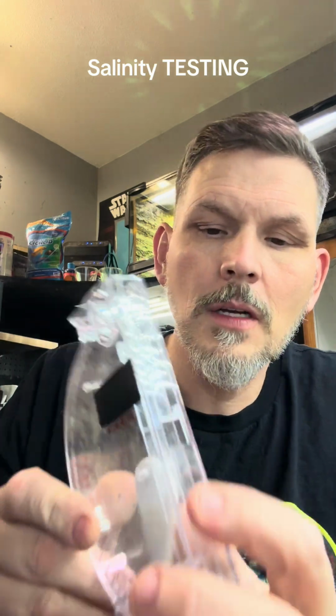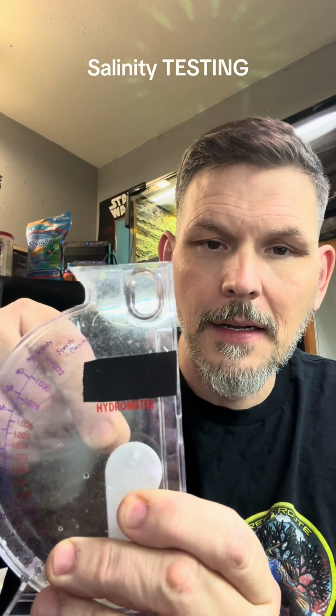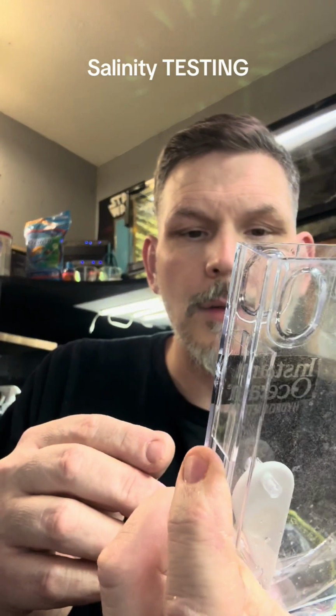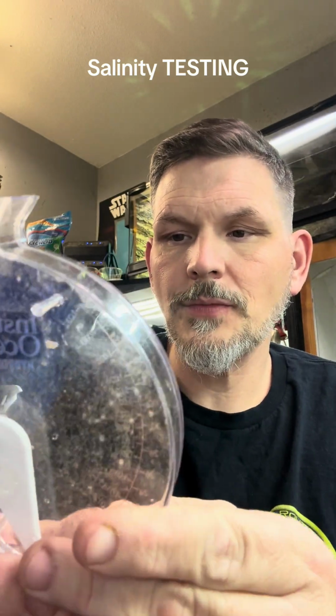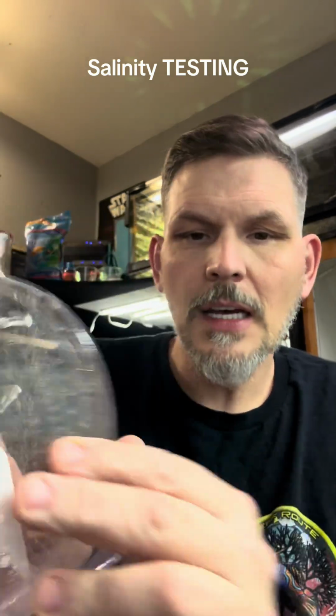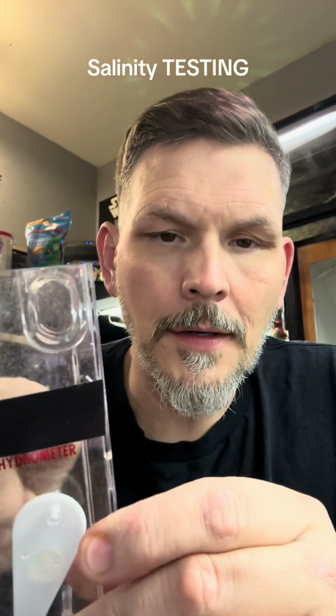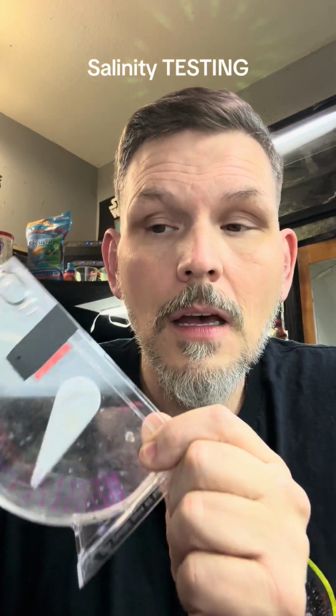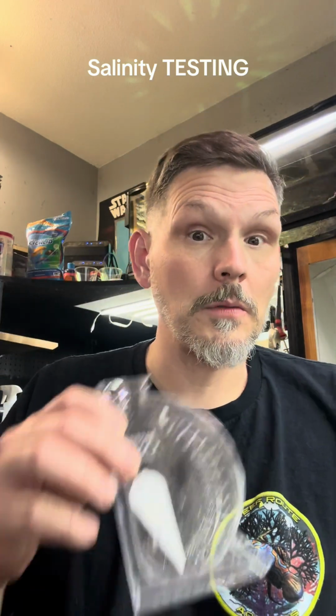Now, I know a lot of people say, well, just take a pen and stick a pen in there and knock the air bubbles out. No, because there's a check in here too. So when you stick that pen in there, you're displacing the water. It's running out this side right here, right? It's only supposed to be X high, okay? So it's coming out the side right there. When you're messing around with displacement, it's going to run over, and you're not going to have the same amount of water in here that you should. So knocking them off with a pen or pencil isn't going to work. If this is all you've got, it works better than nothing. But if this is all that you got, start getting into some other stuff too, which we'll check back with that.